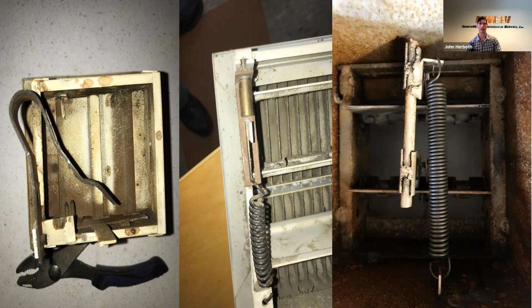So we had to completely disassemble them and actuate it. And because that fusible link had no identification on it, we had to put it back in, assuming it would work. So you can test a few where you can easily get to it and replace, say a 4x4 or 4x8 fusible damper, just to make sure they're working and what temperature they melt at. You're going to run into about 165 as the most standard, and 212 as the other standard. I'm not quite sure when you'd use a 212 application unless it's in some high temp location.